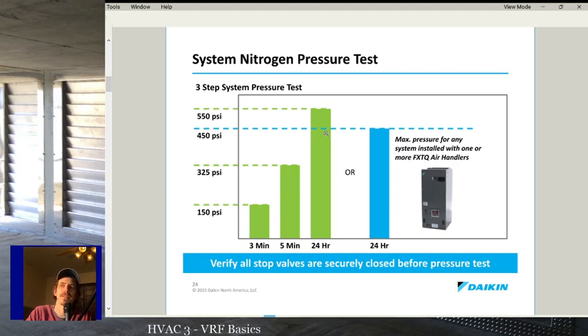If you can only test a system for a short period of time under nitrogen, then make sure that you have a good quality, accurate gauge so that you can see if there's any leaks. If you don't have good gauges, then make sure you let that pressure sit on there as long as possible so that if you have a leak, you'll detect it.